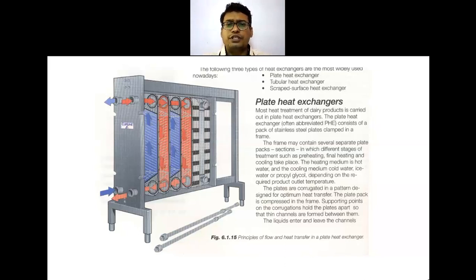The hot fluid which is entering from this side is specifically designed with certain gaskets so that it will not enter this plate. It will only enter this plate. Similarly, in the alternate plates, the hot fluid and the cold fluid will be there.